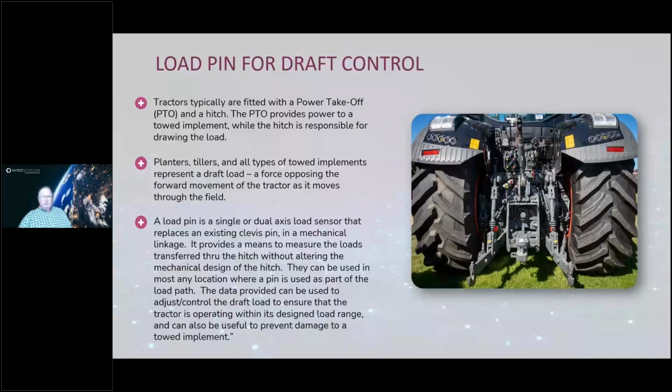Basically, what we would employ here is a load pin. It might be a single axis or it could be a dual axis load pin, depending on the application, which replaces an existing clevis pin on the hitch. This allows us to directly measure the applied loads that are being transferred through the hitch.